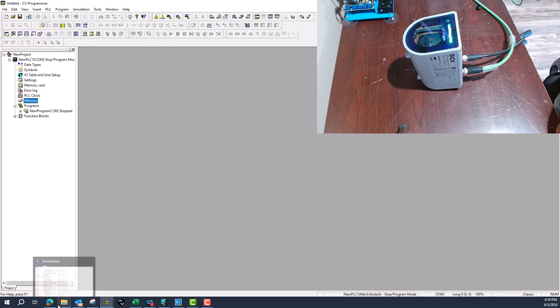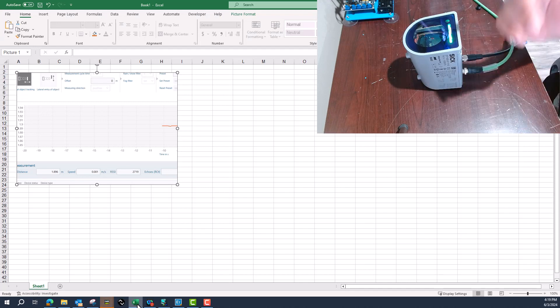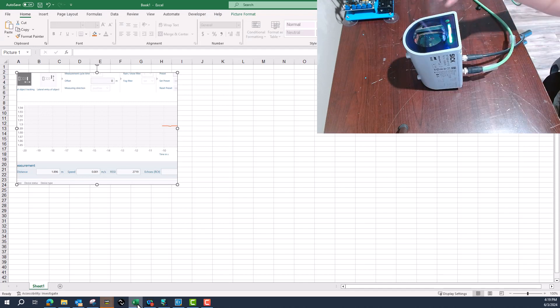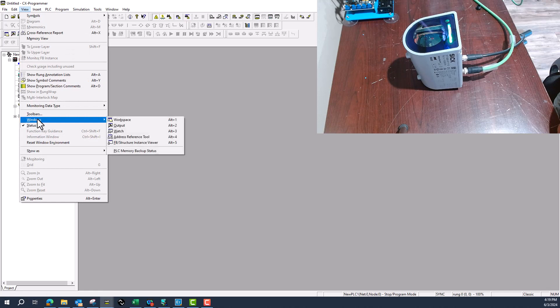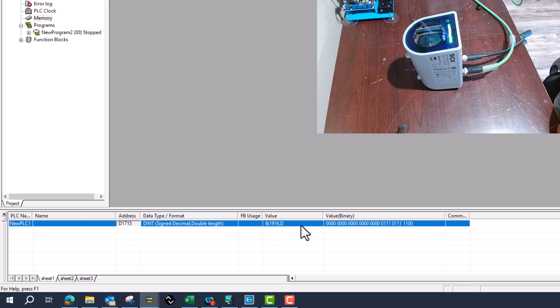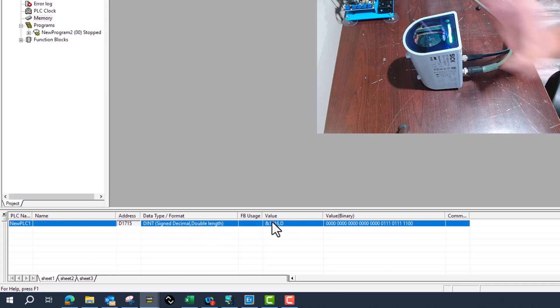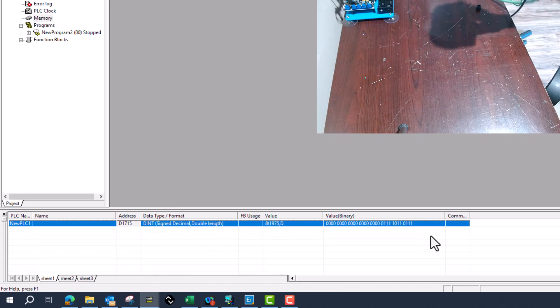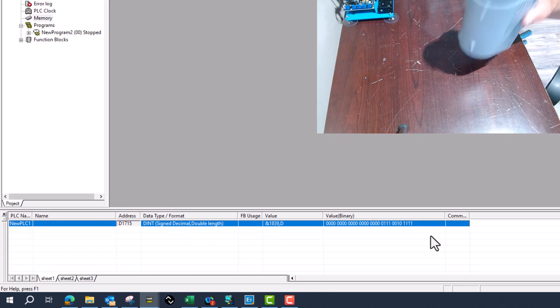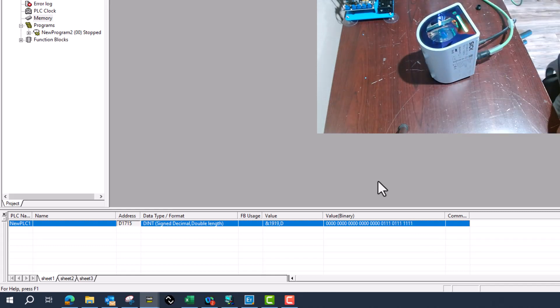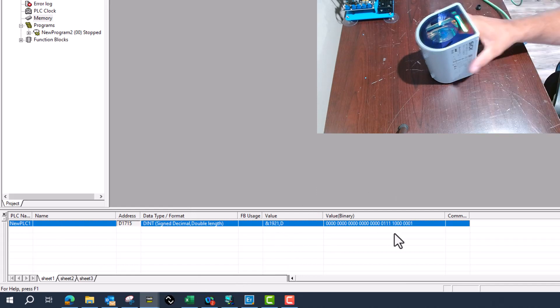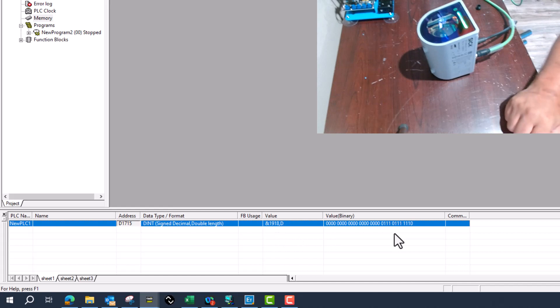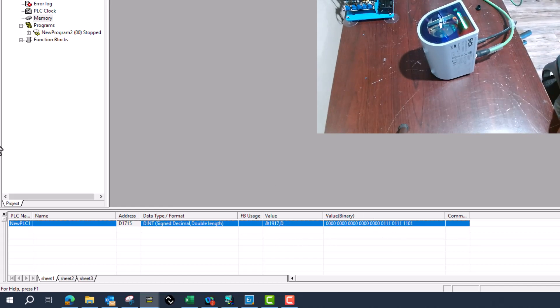Looking at the distance from here, looking up in this place is 1.9 and we were at 1.86. I can come here in my watch table, type in D1715. You see I've got it there. As I move it and start pointing to different spots, that number increases. That's how you take the DT1000 and throw it in the PLC and map it over Ethernet/IP. Hope this helps.